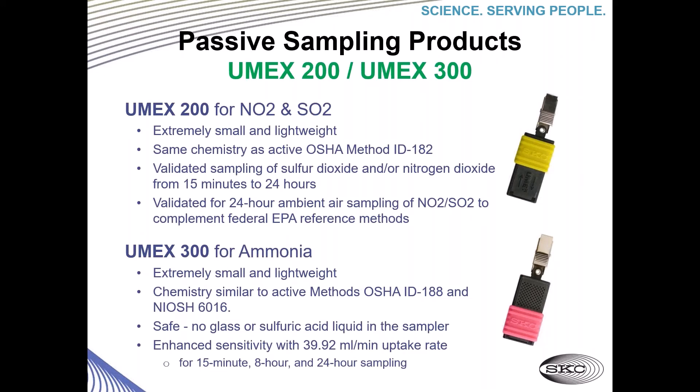In the Umex line we also have the Umex 200 for NO2 and SO2. Same design, same benefits. It uses the same chemistry as the active OSHA method ID-182, with validated sampling of sulfur dioxide and nitrogen dioxide from 15 minutes to 24 hours, and validated for 24-hour ambient air sampling for SO2 to complement federal EPA reference methods.